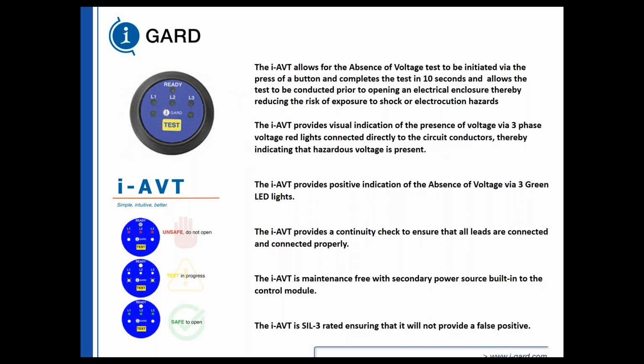The i-Gard i-AVT allows the absence of voltage tester to be initiated via the press of a button that completes a test in 10 seconds and allows the test to be conducted prior to opening electrical enclosures, thereby reducing the risk. This is the new technology that we want to use moving forward to ensure less people get hurt, less people get killed. A mind shift has to take place for people to go home and perform their work under safer conditions. What we've done in the past has been proven not to function properly.